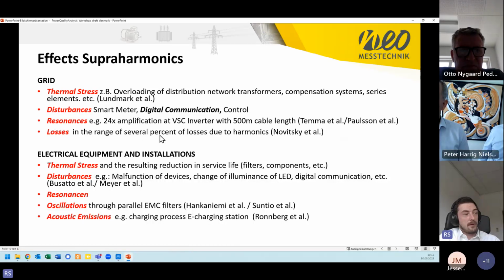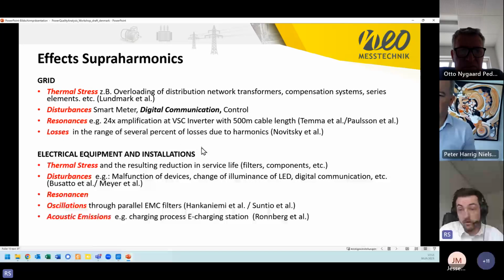Regarding disturbances, smart meter technology uses power line communication, and the digital communication is somewhere in this frequency spectrum up to 150 kilohertz. So if there are supraharmonic emissions in the grid, we have problems with the digital communication. We saw that half of the smart meters, for example, were not reachable because of disturbances in the grid, so control is not possible, among other issues.